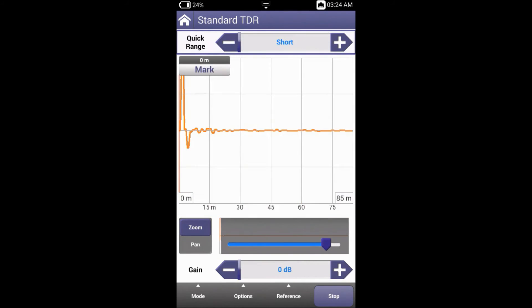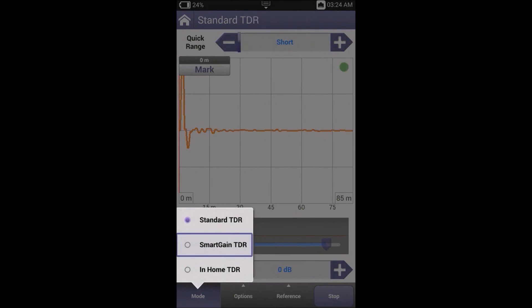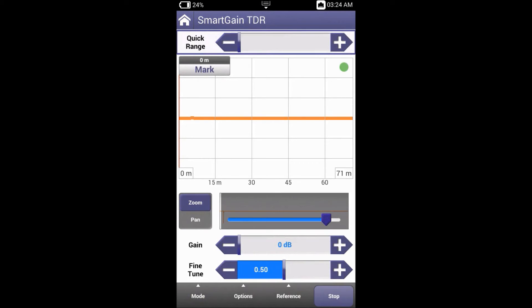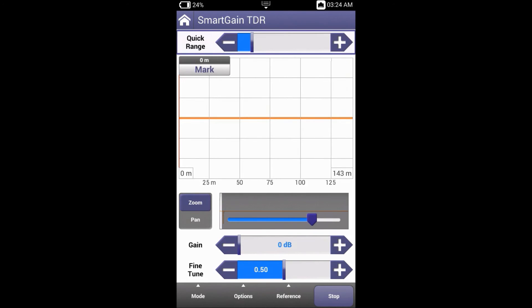Let's now have a look at the smart gain TDR function by pressing mode and going down to smart gain TDR. Smart gain drives the complexity out of running a TDR. Using quick range, smart gain automatically controls gain, pulse width, and zoom features, giving the user the ideal combination of settings. Smart gain incorporates JDSU's patented time-varying gain to eliminate clutter and focus gain at the trouble location.